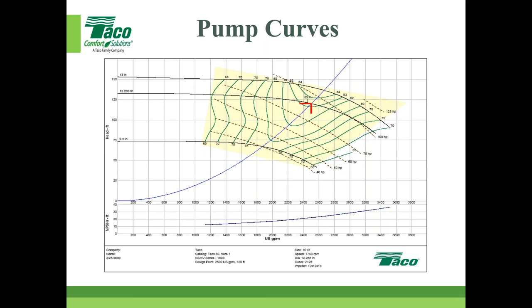Now you can look up that pressure differential on a pump curve and you can determine what the GPM is, assuming that you know what the impeller diameter is. Right. You need to know, and that should be on the tag of the pump. It should show you the impeller diameter there. So that information needs to be there as well. But yes.